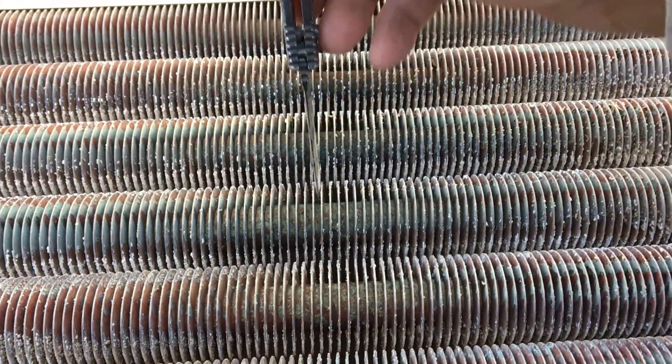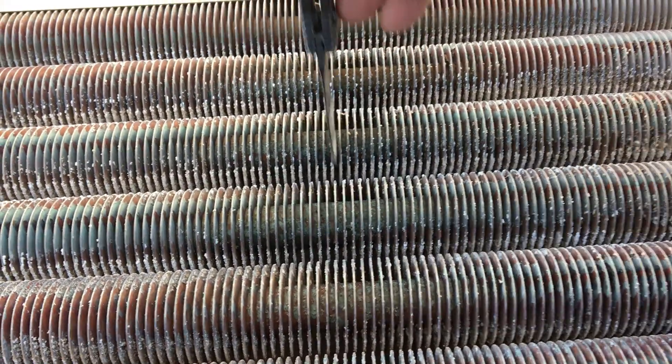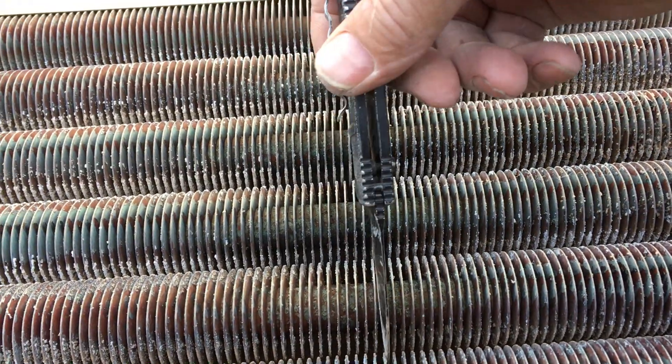This is caused by dirty burners, or sometimes if your combustion air source is from a dirty area. I've even seen some of these boilers that were installed in a laundry room, and somehow the chemicals that were used combined with the flue gases really coated this very badly.